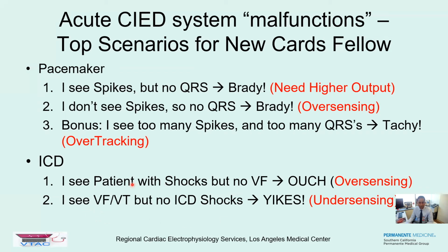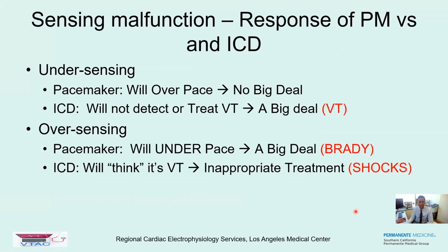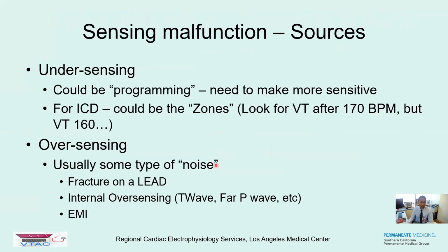Last but not least, we talked about a scenario where a patient is in VT but not getting shocks, so it's undersensing. Let's look at it differently. A pacemaker, if it undersenses, will overpace - if it doesn't see a true rhythm, it'll pace right through it. That's not a big deal. It's oversensing that causes underpacing, and that is a big deal. However, for an ICD, if it undersenses, it won't treat VT, and that's a big deal. If it oversenses, it will shock. Complicated - let's simplify it as much as we can here.